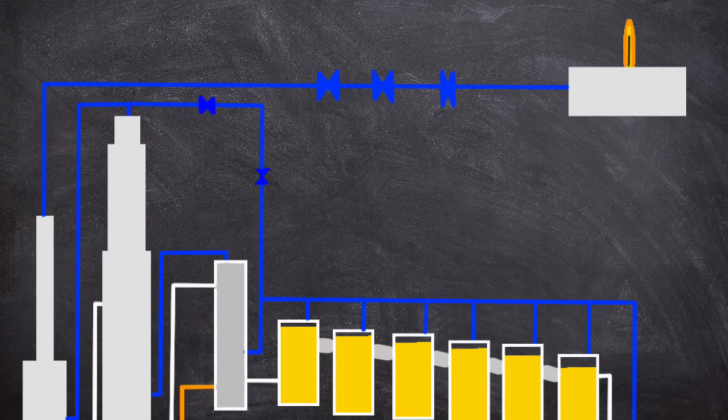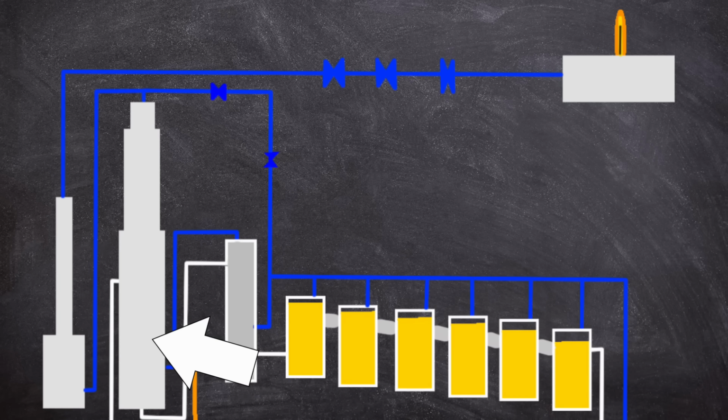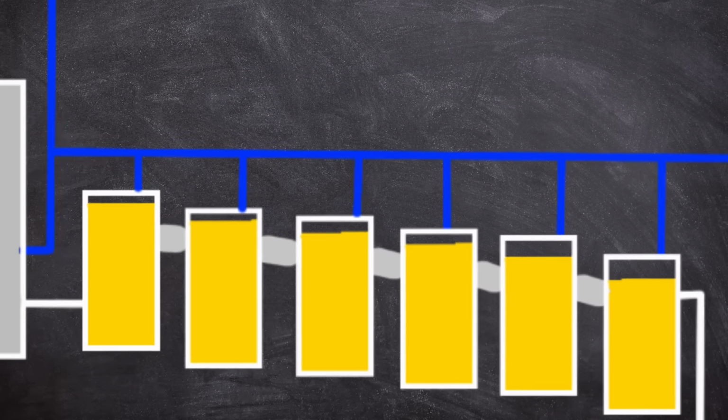During the reactions, some gas is given off, and this is routed back via an off-gas line to the heat exchanger and then to the atmosphere via a cooling tower, scrubber, absorber, and a flare. The off-gas lines serve to equalise pressure in all the reactors. Safety valves on each reactor were also provided, which would vent gas to the scrubber and flare, and this was set at 11 kilograms per centimetre squared.